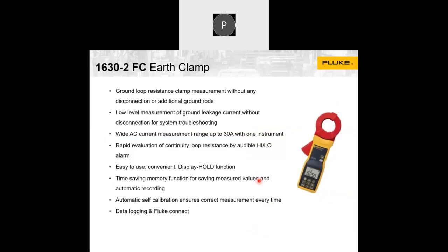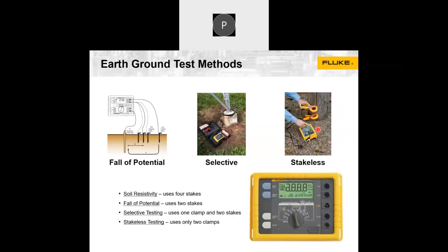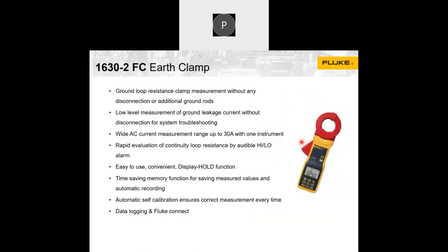Another method of earth leakage testing is the ground loop resistance clamp. This clamp actually has two portions: a sourcing clamp and a measuring clamp, and it works exactly like the stakeless method. With just two clamps in a very small footprint, you can clamp onto any of the earth wires and find out the leakage or earth resistance. This is a very critical device to deploy in your system to catch malfunctions.